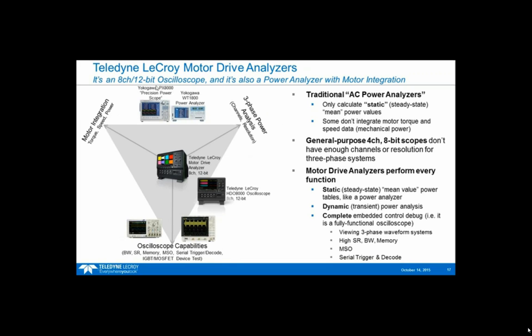For three-phase and mechanical power analysis, the better power analyzers have a motor integration option so they can measure mechanical and electrical power. But typically you'd have one of these tools and one of those, and they don't communicate well with each other—they're very different instruments. Some of you may have an 8-channel scope like the HDO 8000, or perhaps own the Teledyne Lecroy motor drive analyzer, an 8-channel 12-bit platform that integrates motor analysis—basically three-phase electrical and mechanical motor analysis.